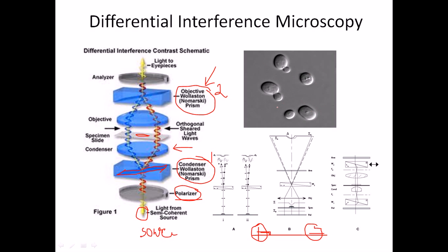But if we place a specimen — for instance, a cell culture of yeast Saccharomyces cerevisiae — what happens when the light beams pass through? The specimen deflects some amount of both light beams, slightly changing their phase transition. The diffraction changes, causing the beams to interfere with each other, generating different types of light beams. When the second Wollaston prism gathers these beams together, the analyzer can no longer block all of them.